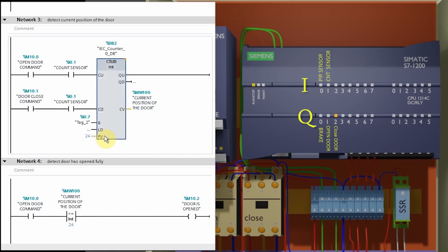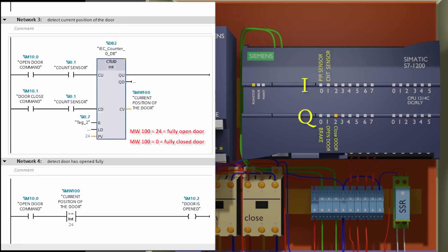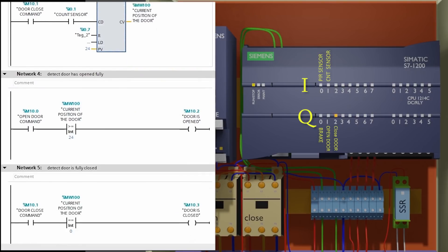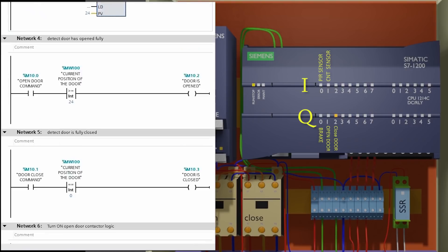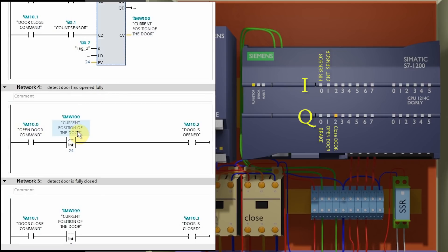The preset value of the counter is 24 because it requires 24 pulses to fully open the door. If the current value of the counter is 24, the door is fully opened; if it is 0, the door is fully closed. Network 4 is used to detect if the door has opened. A comparison instruction compares the current counter value with 24 — if it is greater than or equal to 24, it turns on memory bit M10.2, which indicates the door is fully opened.